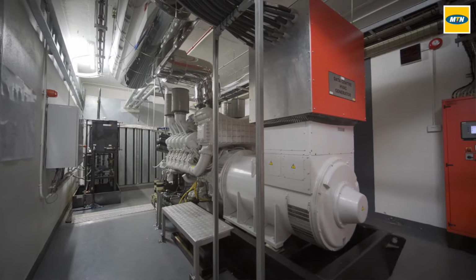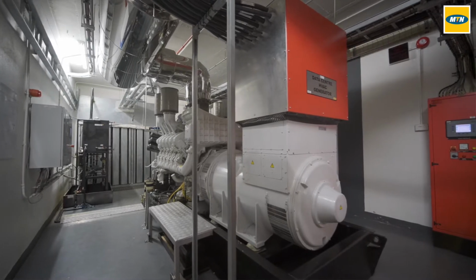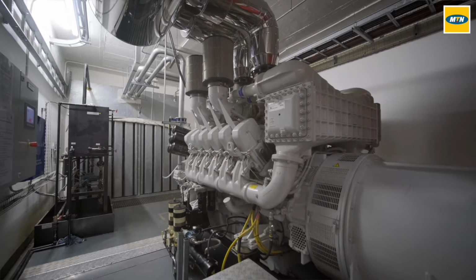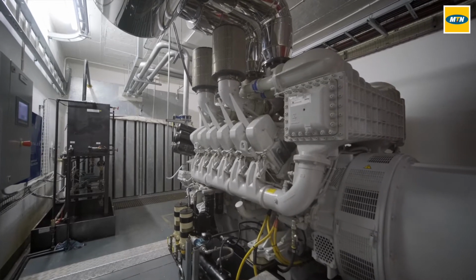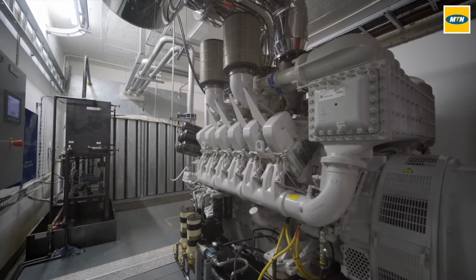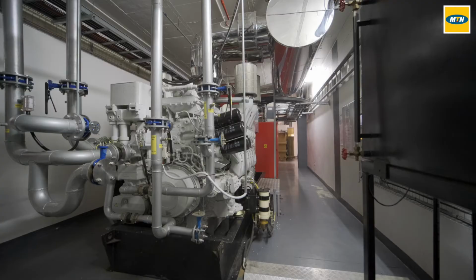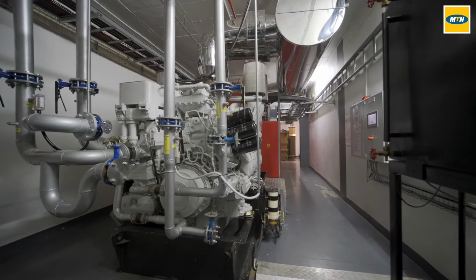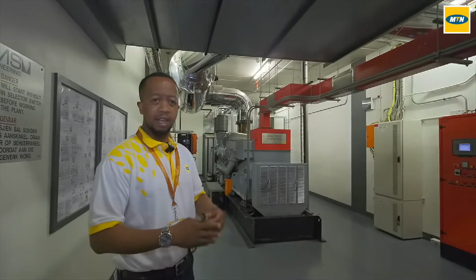The way our system works is that they all start up individually. They take up the load for side A of the electrical installation, side B of the electrical installation, and the HVAC side of the electrical installation. Once the synchroscope has tied in, they all sync up, close on the bus, and run in sync.